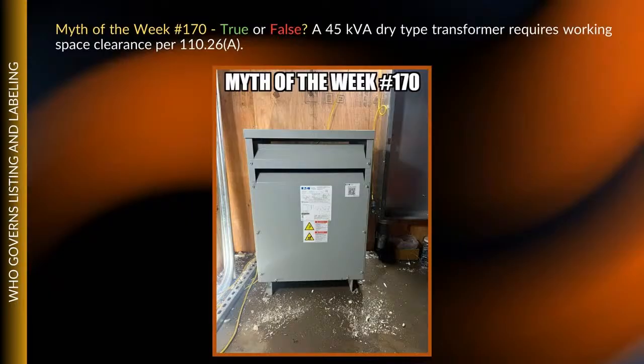Working space and access to and from. When you look at 110.26, it's going to talk about working space, and it'll say access and egress to and from the workspace shall be provided and maintained about all electrical equipment. I don't disagree with that. But when you're looking at that, the key word that it starts off with in 110.26 is working space.